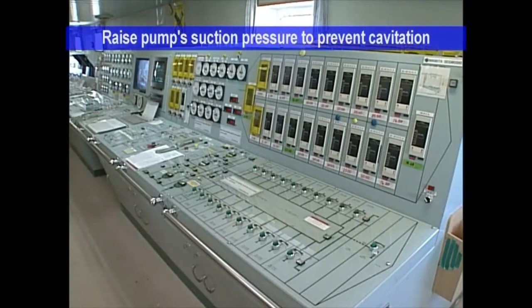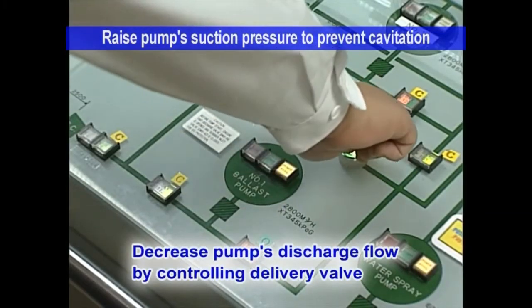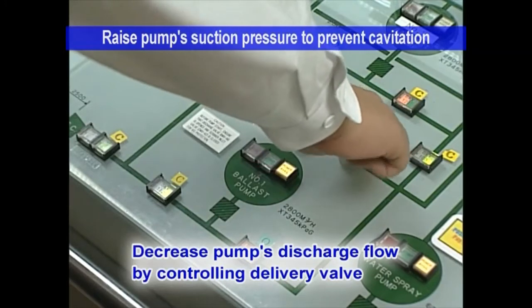To prevent cavitation, raise the pump's suction pressure. In terms of pump operation, decrease the pump's discharge flow by reducing the discharge valve opening.